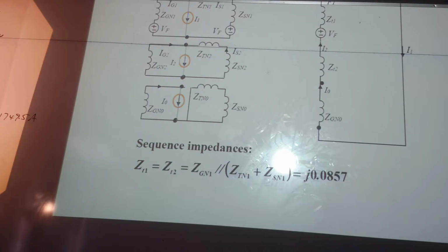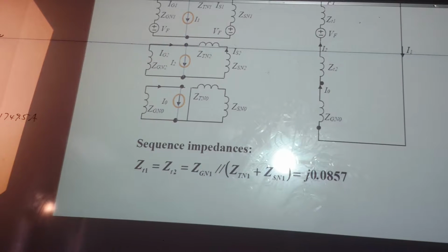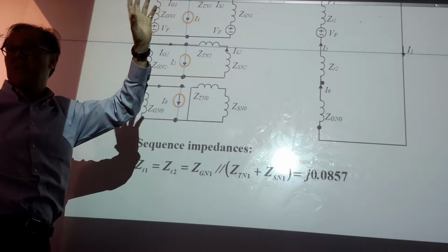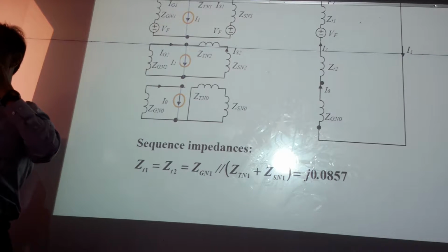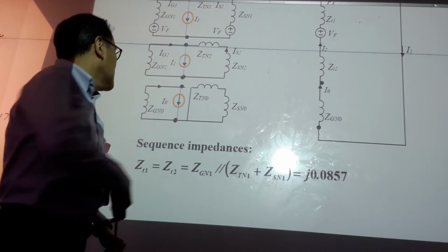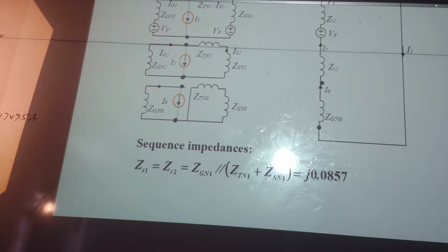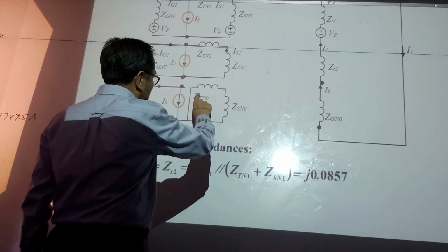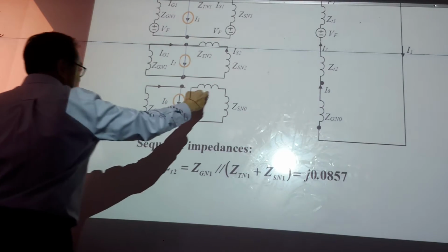Okay or not? Then this one, like what we have said, because it's delta-Y, it's broken here. Can you see it's broken here? For this one, you have to consult his transformer table for the zero sequence. At one time I also showed it to you, so I don't want to go back to that table again. It's there. So this is the Y grounded, so it supports a current on this side. You can see there's a zero sequence for this system, and this is the transformer zero.